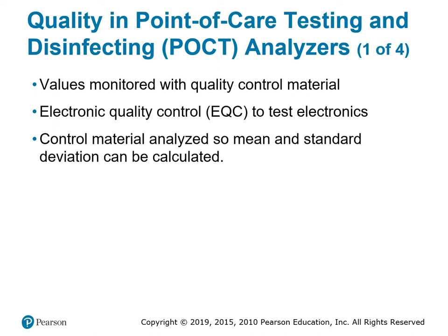we can determine the outcome of something when we account for all the variables. Okay, so the mean on these devices would be the average. Like, what is the average reading for this device? Depending on if it's been dropped, if it's dirty, the batteries are about to die, on average it's going to give this reading, regardless. The standard is what we need it to be. All right, the mean and the standard should complement one another. All right, so that's how you think about that.